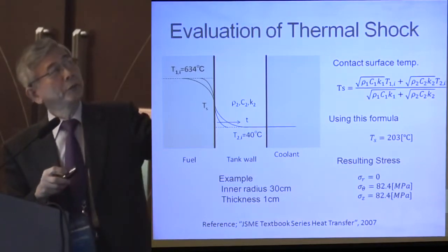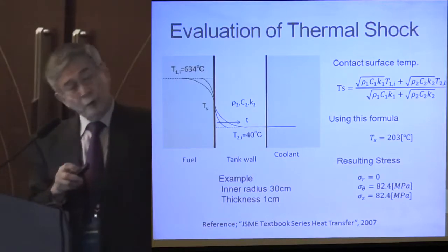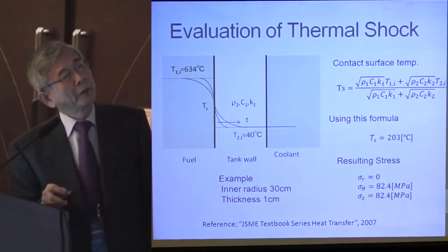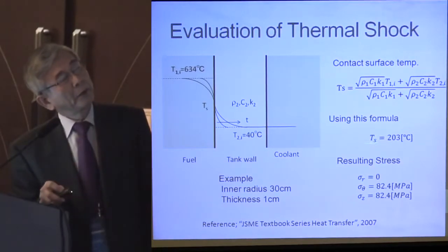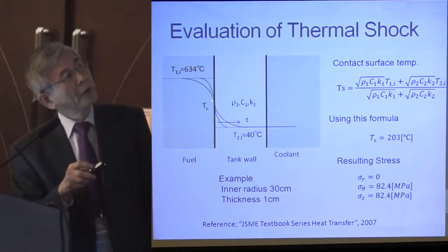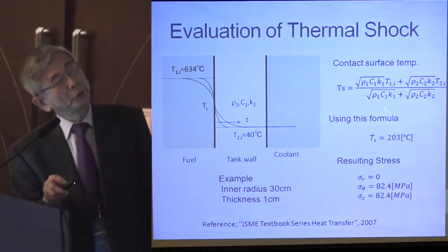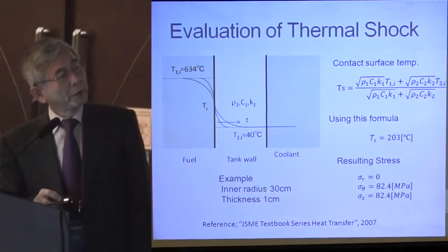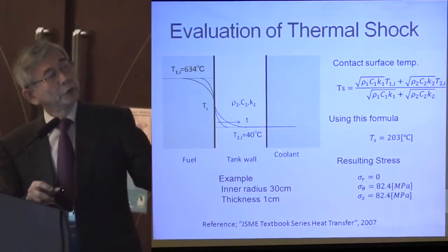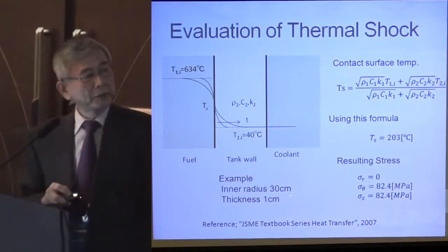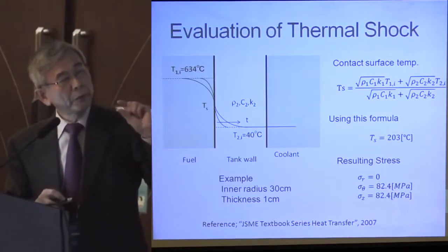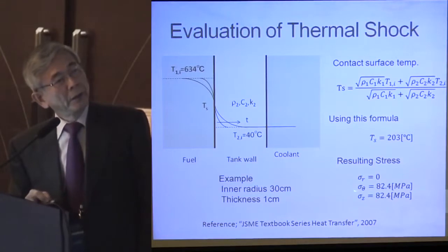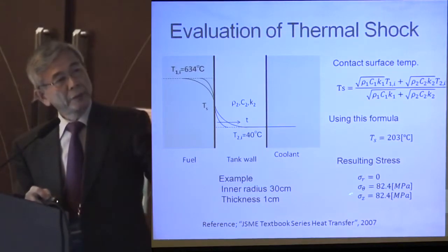This is the average fuel temperature of normal operation, and the water temperature is 40 degrees Celsius. The surface temperature is evaluated to be around 200. And for the tubing inner radius of 30 centimeter and the thickness 1 centimeter, we can calculate the stress.